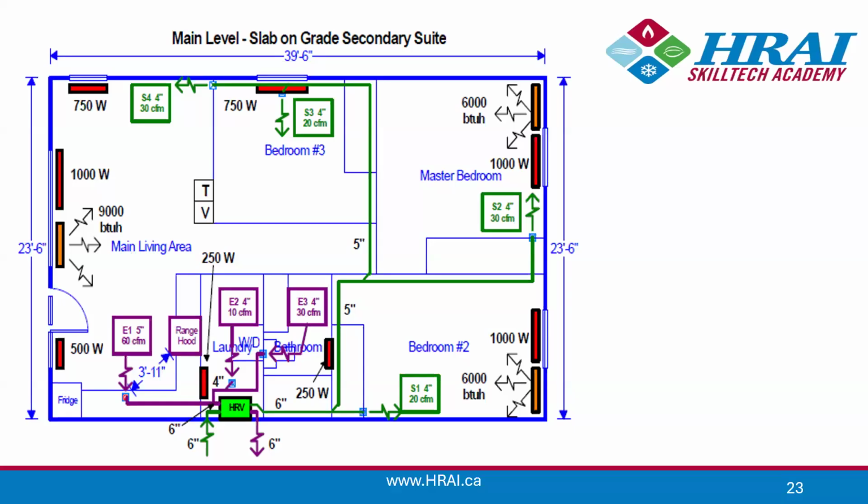We've got a fresh air outlet in this bedroom. We come across in a bulkhead and deliver to the master bedroom, and then again over in a bulkhead to hit the bedroom across the way and the living area. So what we're saying in the new code is you'll no longer need supply outlet 4 here because you've got the air intake here. And so the theory being that, from virtually every other point in the dwelling unit, fresh air is being delivered, and it should still sweep through the space with some degree of effectiveness. So S4 can come out.